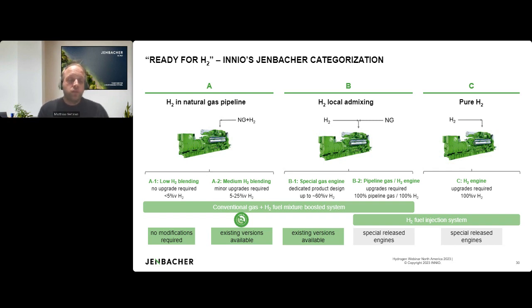For the range of 5 to 25% by volume of H2 added to the fuel, the physical properties of H2 become significant. Here we have a hydrogen blending kit available. We need a sensor to tell us the H2 concentration, or it can be an external input, but we need to know the H2 concentration in the fuel. Then we can adapt the engine operating points via software to make sure the engine operates as it's supposed to on mixtures up to 25% H2.